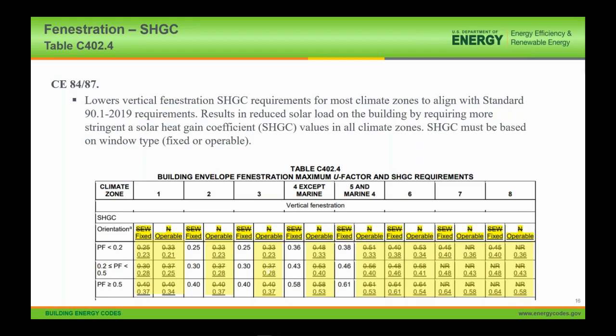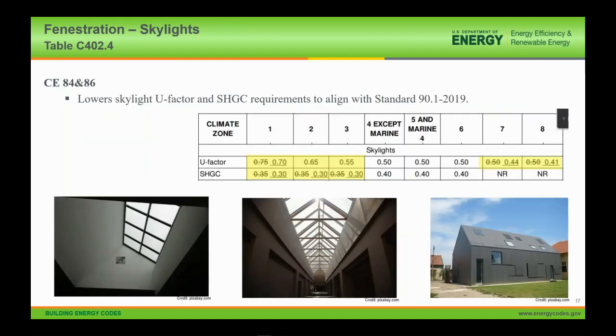It's also, I think, important to note here that for the first time, vertical fenestration in climate zones 7 and 8 will be required to meet maximum solar heat gain coefficient requirements. In addition to performance changes for vertical fenestration, there are also improvements in the U factor and solar heat gain coefficient requirements for skylights. And these changes impact buildings in climate zones 1 through 3 and climate zones 7 and 8.